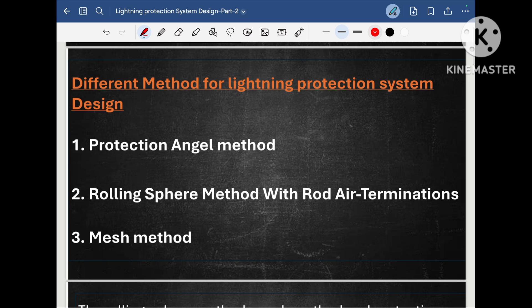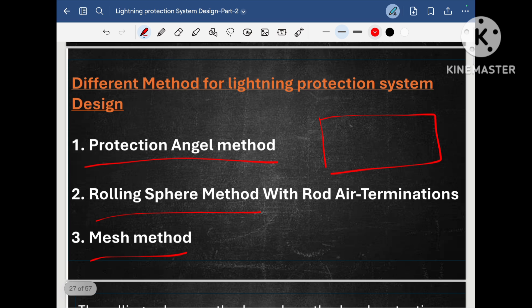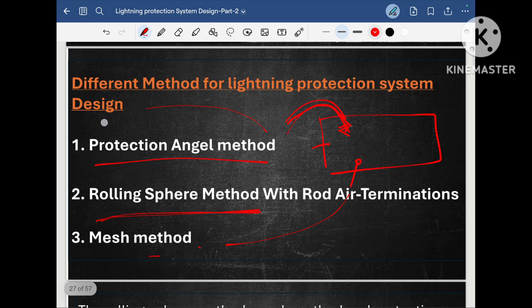There are 3 major methods in order to design the lightning protection system: protection angle method, rolling sphere method and mesh method. For a single particular project, we can design the lightning protection system using all 3 methods. Like for a particular project, we can go for the rolling sphere method for some part and for some portion we can also go for the protection angle method.